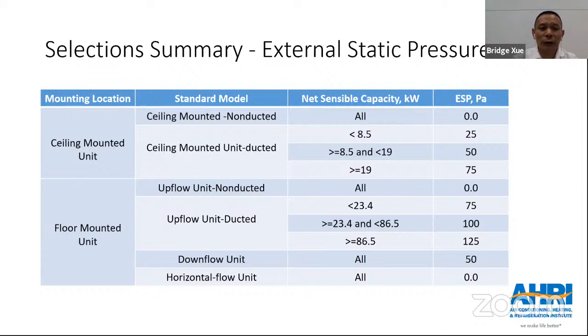So for the floor mounted unit, they have an upflow unit non-ducted, so for sure 0 Pascal will be applied. For the upflow unit with ducted, same, including three ranges, right? So you can see here, the unit will be big, then ceiling mounted. The first range is lower, we call this the small unit, from 23.4. So 75 Pascal will be applied. For the medium size unit from 23.4 to 86.5, 100 Pascal will be applied. For the largest unit, which is greater than 86.5, 125 Pascal will apply. For the downflow unit and the horizontal flow unit, downflow unit, 50 Pascal will be applied. Horizontal flow, because there is no ducting, right? So mainly, this is about standard models, okay? So 0 Pascal will be applied.